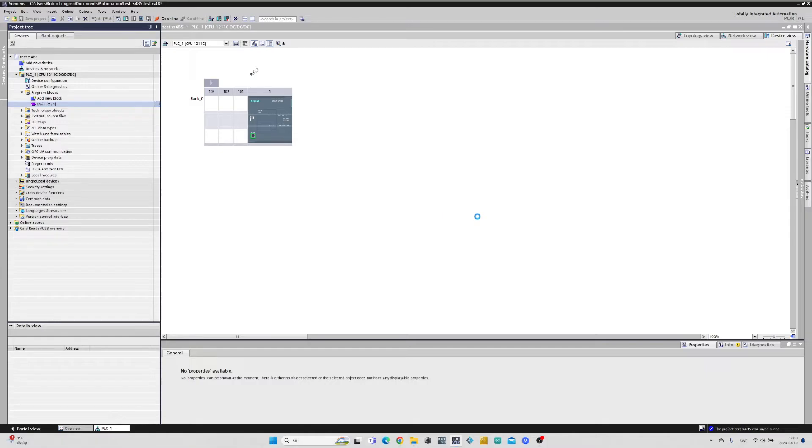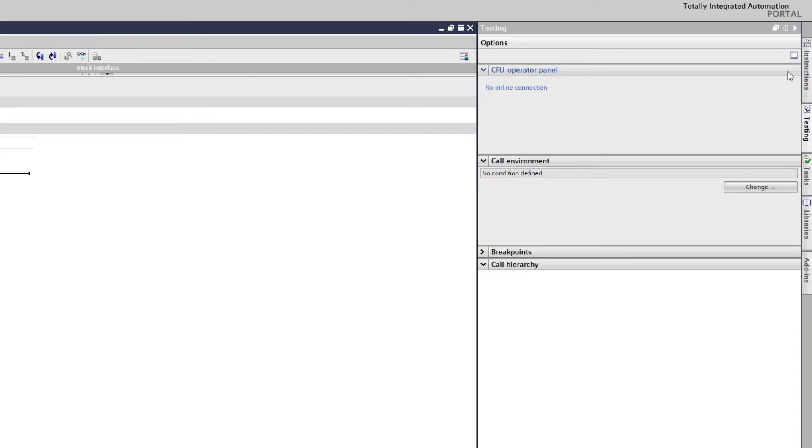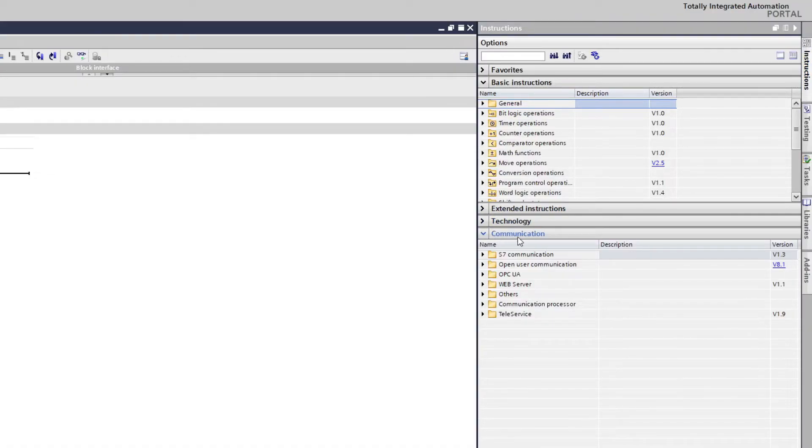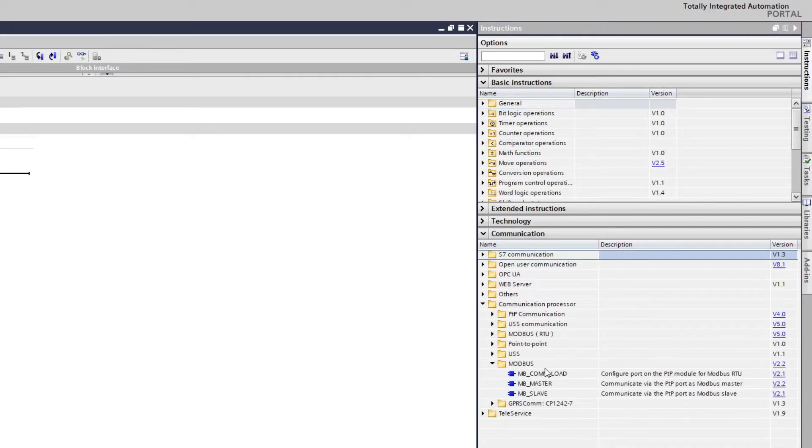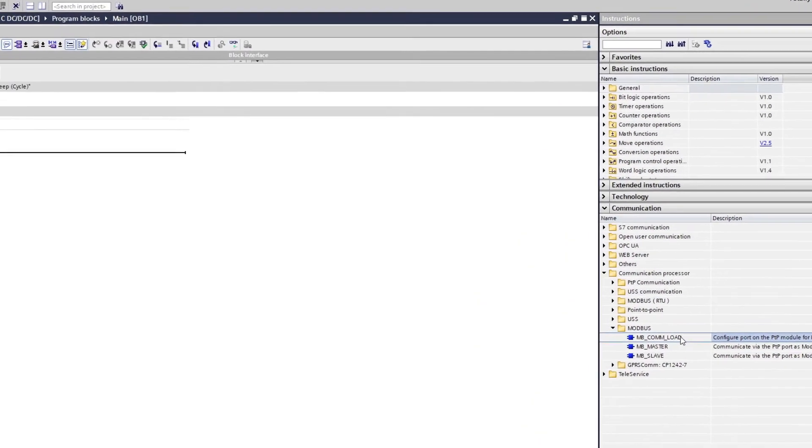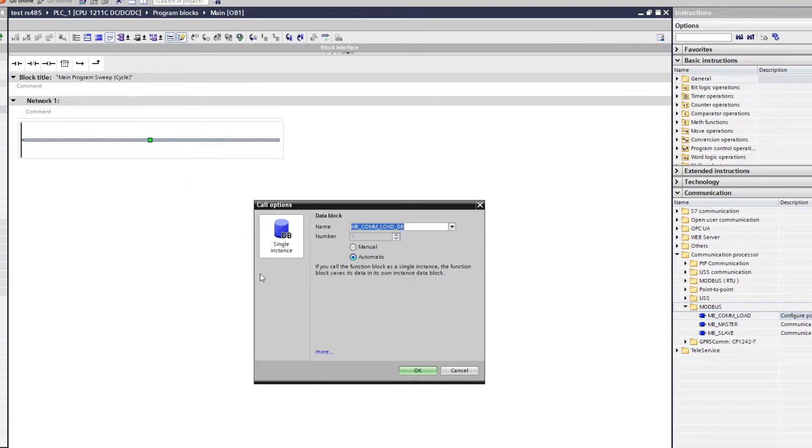We can now go to the main block and do some programming. If we open up the Instructions tab, then under Communication we find a map called Communication Processor. In here we will find the Modbus map with the Modbus RTU blocks. We will need to add one MB_COMM_LOAD block and one Modbus master block.